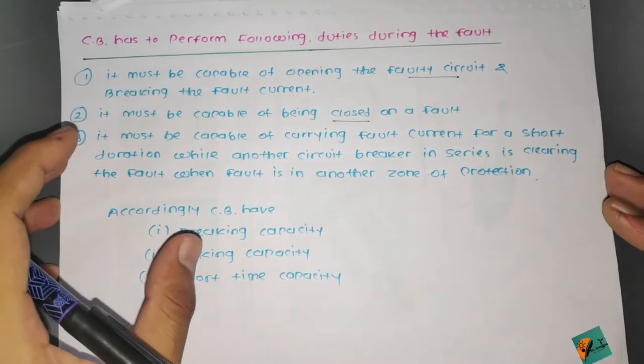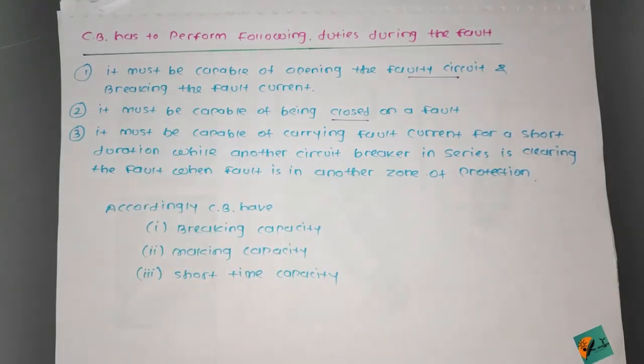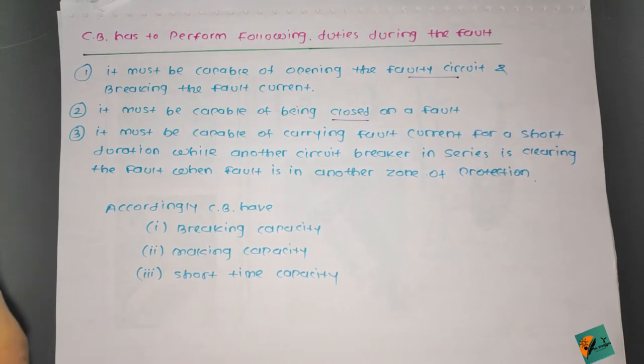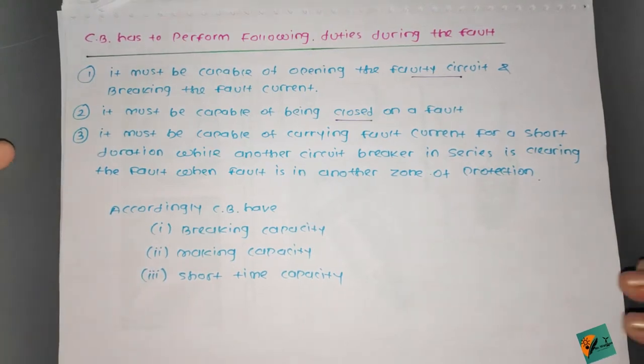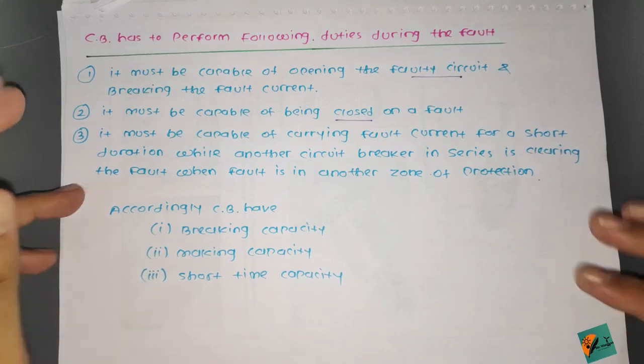One circuit breaker should wait while another circuit breaker in a different zone handles the fault. Even though the fault current affects the first circuit breaker, it should not operate immediately — it should only operate after a time delay. If circuit breaker one fails to operate, the second one will come into operation. Accordingly, circuit breakers have breaking capacity, making capacity, and short time capacity.